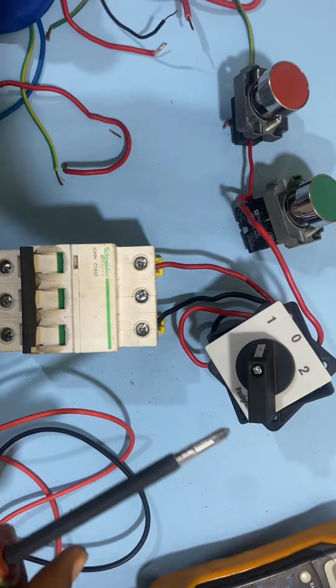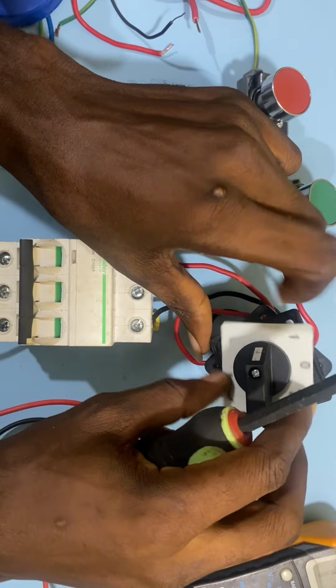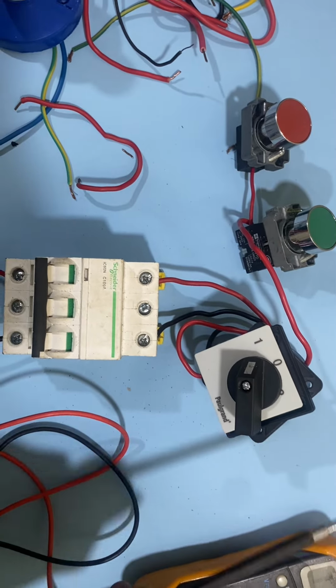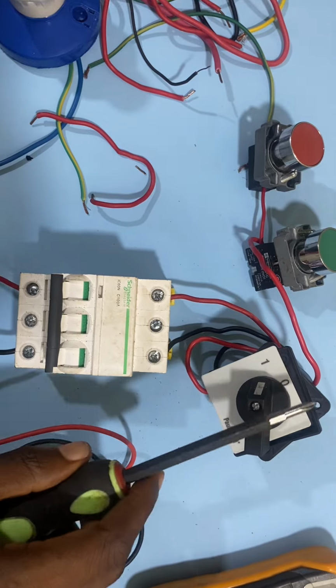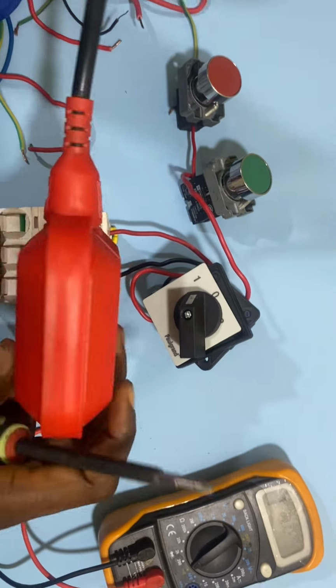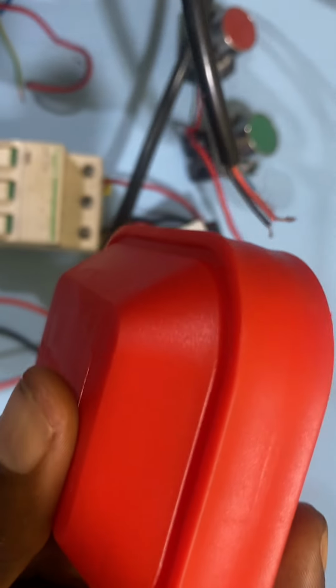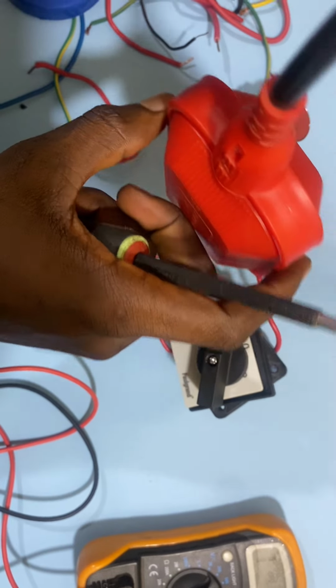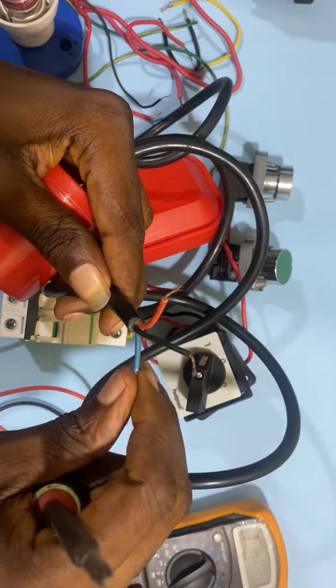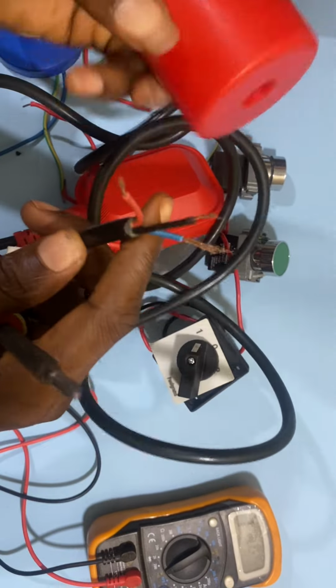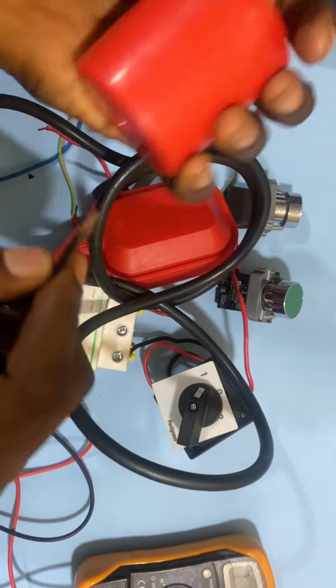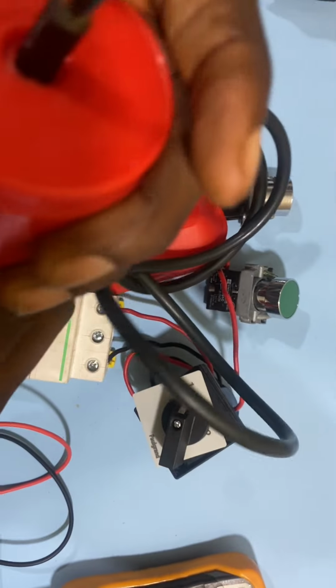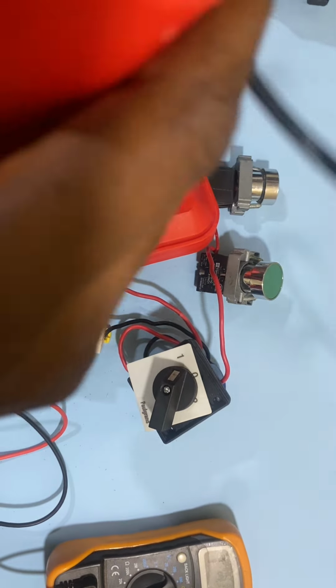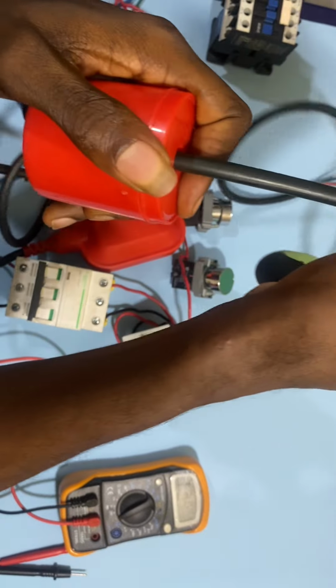So now I'm going to connect a float switch as another switch, so that we can use it to automatically pump the water. So I'm going to connect the live wire of the float switch to the selective switch here. But before doing the connection, when the float switch is at this position, it means that the water has filled the tank, but when it is down, it means that there's no water, so the water should start pumping. And how do I know that? From this terminal of the float switch, we have the normally open, we have my common, and we have normally closed. This is what we use to determine at what point the float switch should sink and stop floating, so as to take the knob up or take it down for the pump of water.